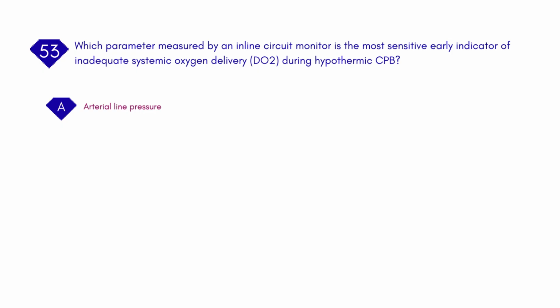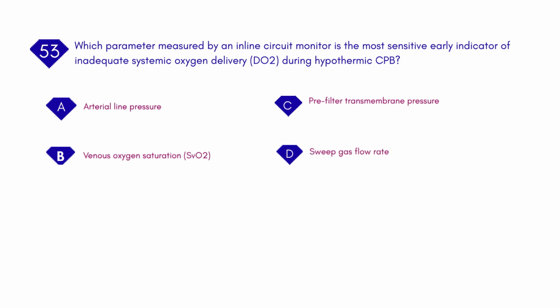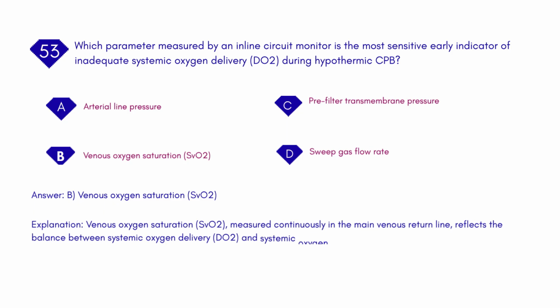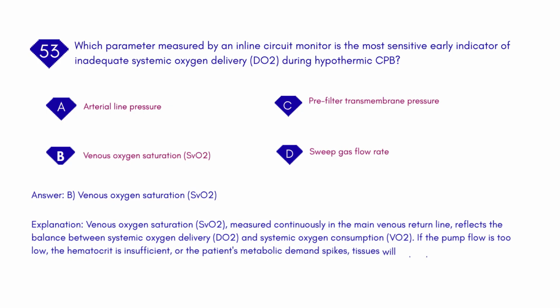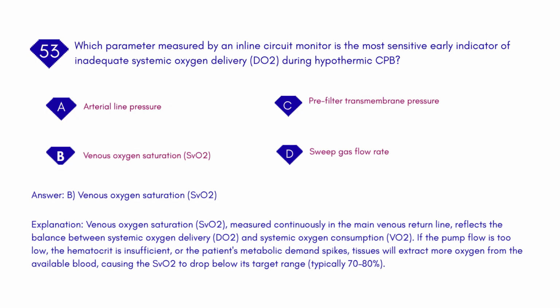A. Arterial line pressure. B. Venous oxygen saturation, SvO2. C. Pre-filter transmembrane pressure. D. Sweep gas flow rate. Answer: B. Venous oxygen saturation, SvO2. Explanation: venous oxygen saturation, SvO2, measured continuously in the main venous return line, reflects the balance between systemic oxygen delivery, DO2, and systemic oxygen consumption, VO2. If the pump flow is too low, the hematocrit is insufficient, or the patient's metabolic demand spikes, tissues will extract more oxygen from the available blood, causing the SvO2 to drop below its target range, typically 70 to 80%.